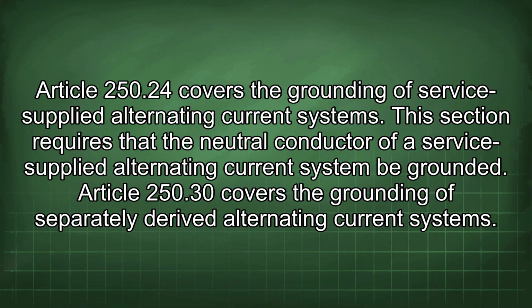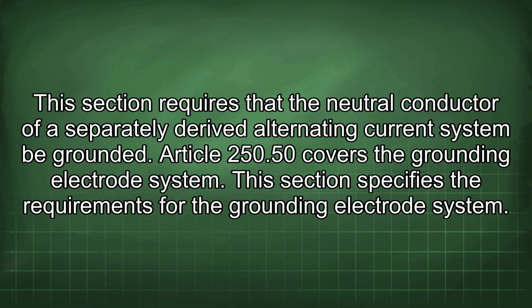Article 250.24 covers the grounding of service-supplied alternating current systems. This section requires that the neutral conductor of a service-supplied alternating current system be grounded. Article 250.30 covers the grounding of separately derived alternating current systems. This section requires that the neutral conductor of a separately derived alternating current system be grounded.